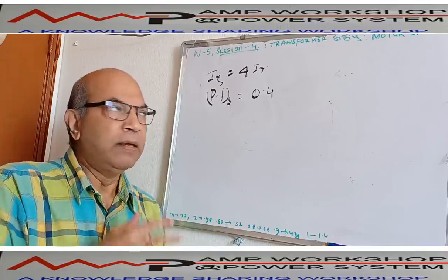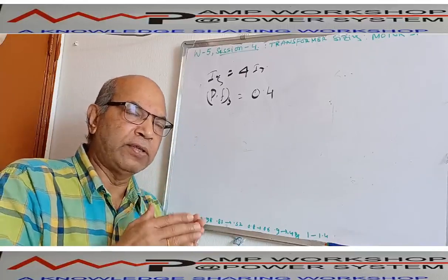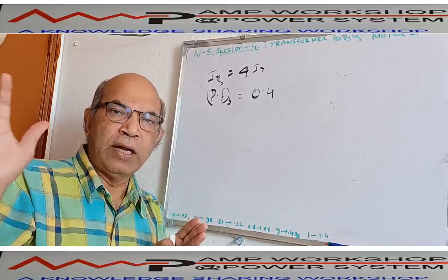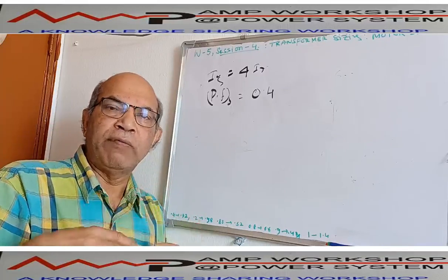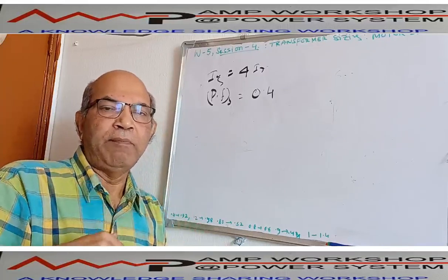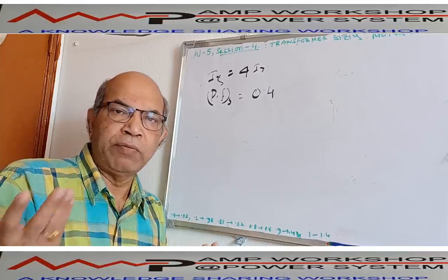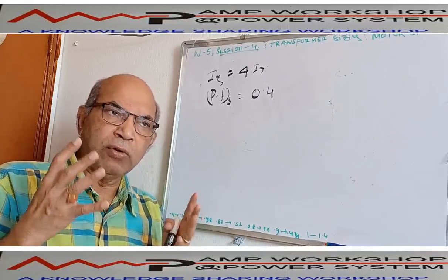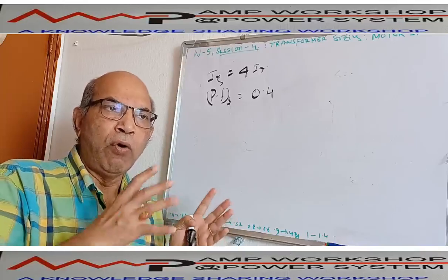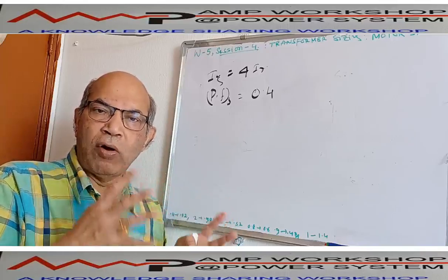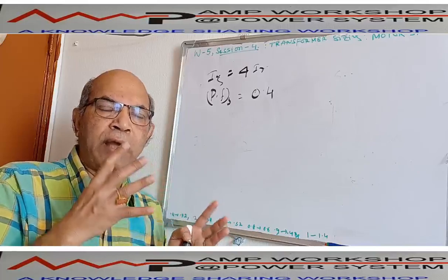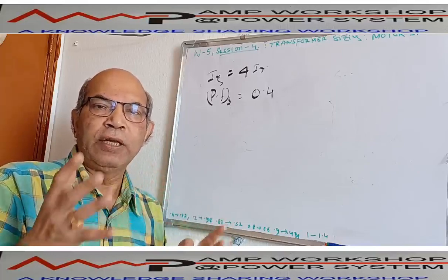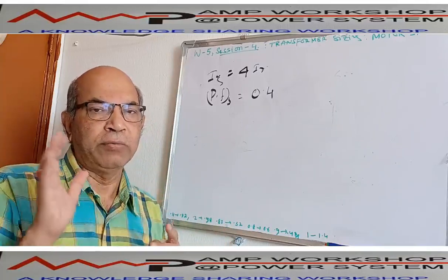That is not there. But in this case, if we consider from the starting point up to the running condition, the motor draws different current at different times, and the power factor also varies from time to time. So we have to size the transformer in such a way that under all conditions, the transformer should be capable of catering the required kilowatt and kVAR under all circumstances.